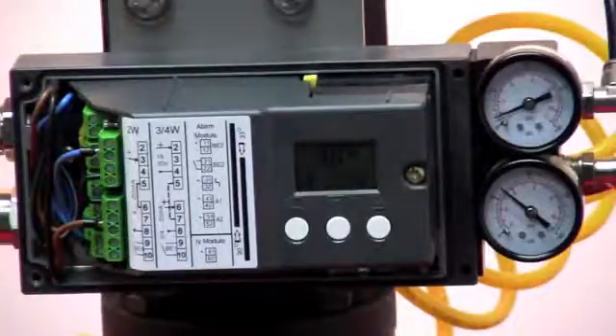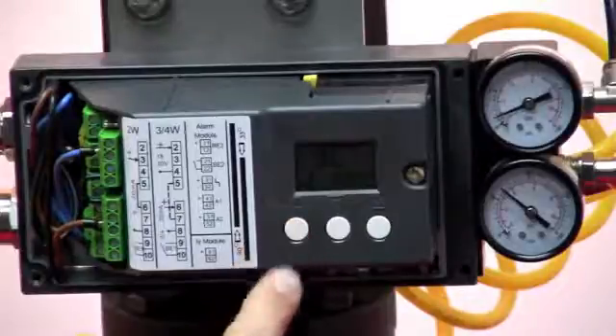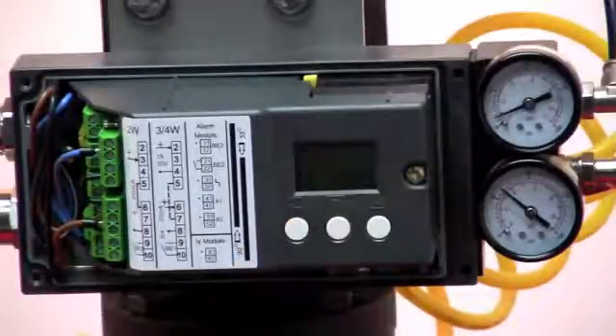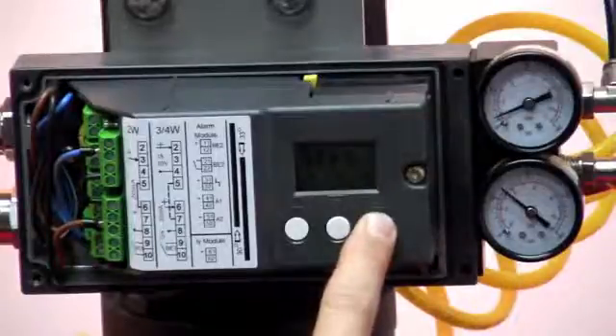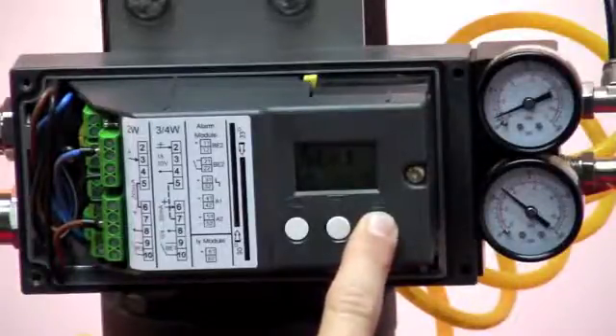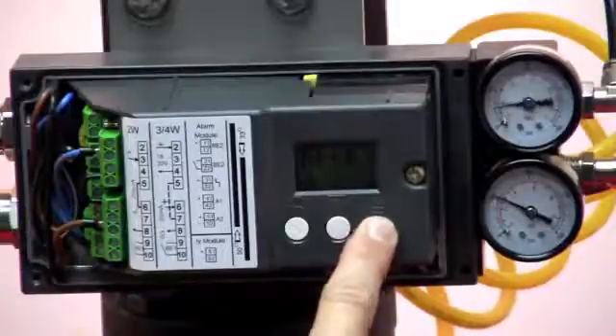And now comes the easy part. You go to menu item four, which is the automatic initialization screen. Press and hold the plus key for five seconds. And then the positioner takes over and does the rest.